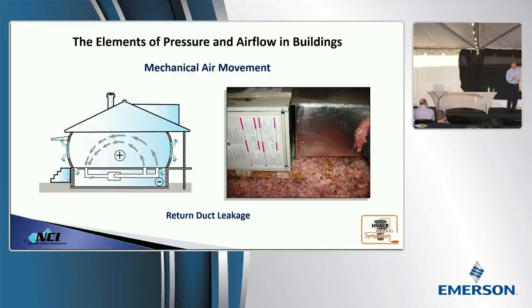You need to dig a little bit deeper and find out why the static pressure is high. Because if you seal an undersized leaky duct system, what's going to happen to the total external static? It's going to go up. You're going to sign the death sentence on the equipment. The heat exchanger will crack, for sure. You may have signed the death sentence on it trying to do something good. So that's a pre-qualifier for any duct sealing.